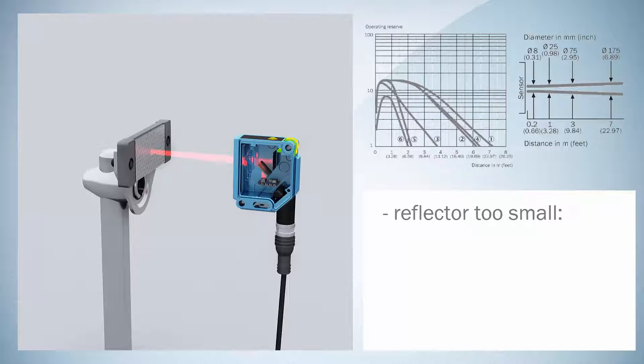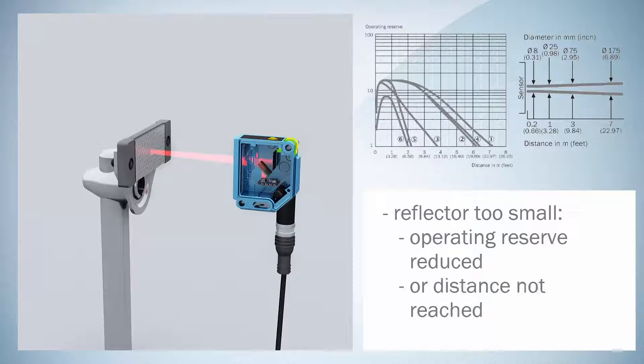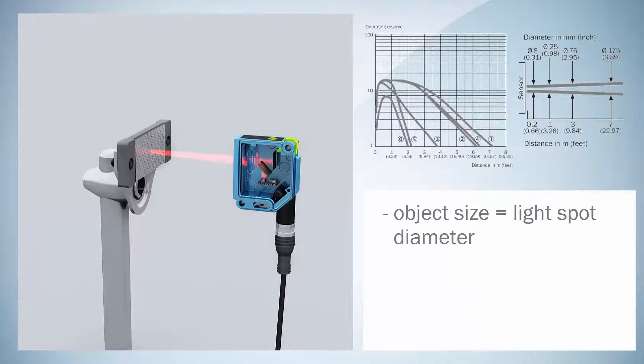If the reflector is too small, the operating reserve is reduced or the operating range cannot be fulfilled. Object size should preferably be the same as the light spot diameter.